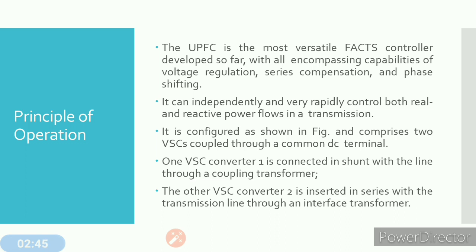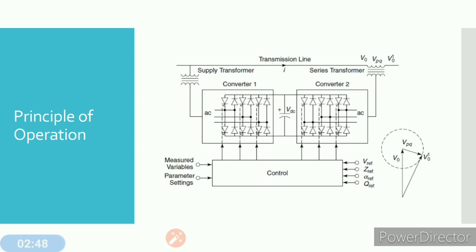The other VSC, Voltage Source Converter two, is inserted in series with the transmission line through an interface transformer. Converter one is connected with the help of a supply transformer in shunt with the transmission line, and converter two is connected to the transmission line with the help of a transformer. Both converters share a common DC capacitor. Converter one rectifies the voltage taken from the supply transformer and feeds the rectified voltage to converter two.